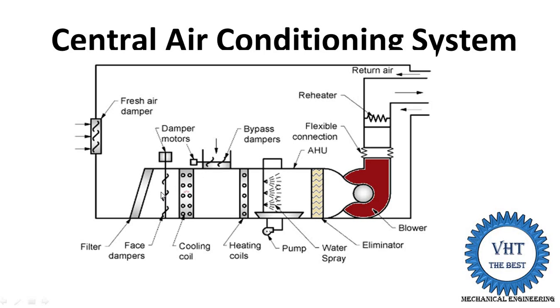This air passes through the cooling coil, where it supplies heat to the refrigerant inside, so cooling and dehumidification takes place. Due to dehumidification, a water tray is placed below the cooling coils, and the collected water is drained outside the system. When only cooling is required, only the cooling coil is operated; the heater and pump are stopped.